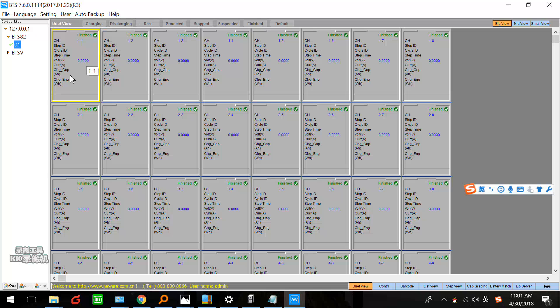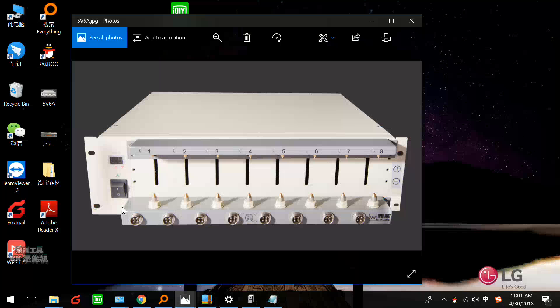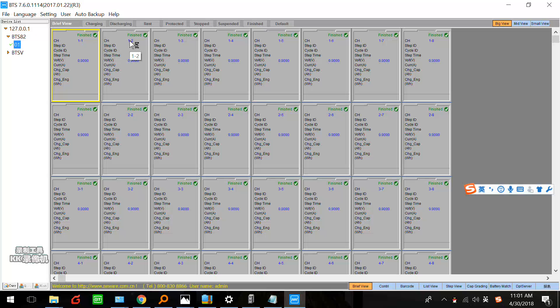We click here — this is channel one, which also means hardware channel one. Channel one here. This is the finished station. Channel one, channel two. This one means unit one, and this two means channel two. This one means unit two, channel two. Unit two, channel three, unit three, channel three. And this is the step ID, meaning which step — like constant current and constant voltage charge step.